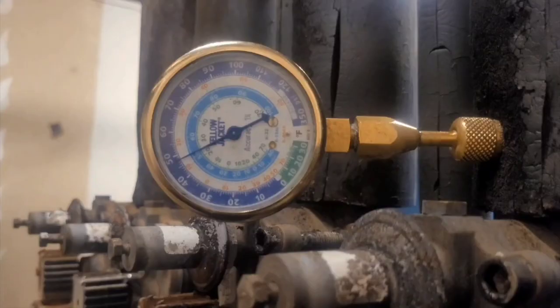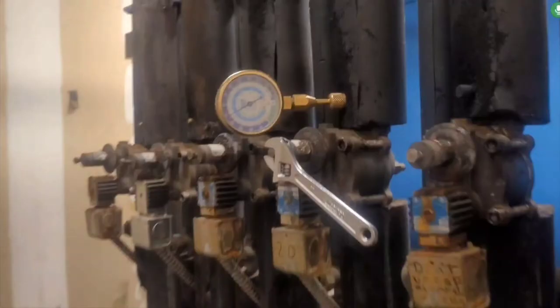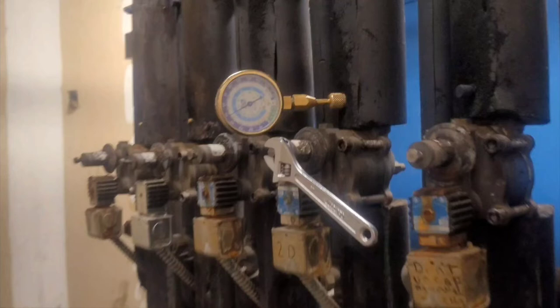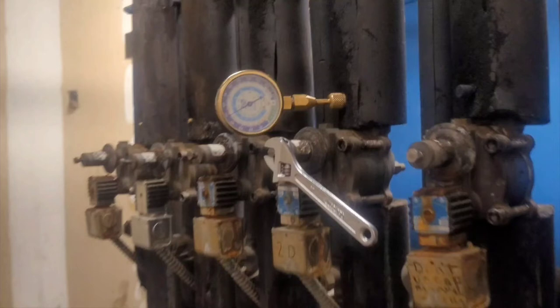On the top of 2D, we've got a pressure of 48. These can be adjusted by rotating the adjustment screw. If you turn it clockwise, it's going to raise the pressure on the inlet. If you turn it counterclockwise, it's going to decrease the pressure on the inlet. Doing that is directly going to affect the case temperature.